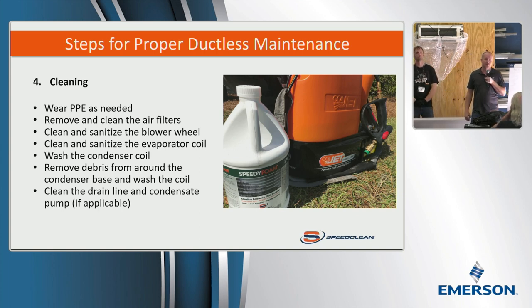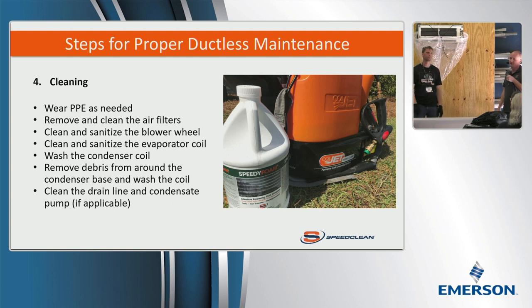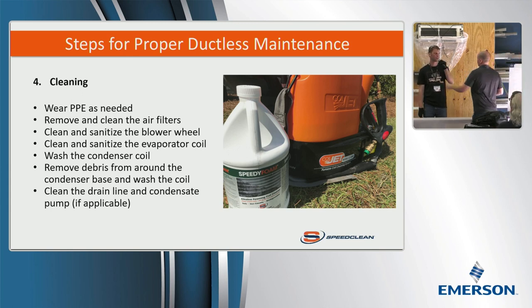No, there are foaming cleaners that are still neutral, or very close to neutral. I don't know exactly what the pH is, but you want something that's not advertised as alkaline. It's generally the strong alkaline cleaners that are the crazy foaming ones, the ones that look really dramatic. But you can still use cleaners that are mildly foaming and still work. Generally speaking, to be safe, I'd suggest using cleaners that specify they're evaporator cleaners—those are your safest ones. They'll be the most neutral and cause the least corrosion. I like evaporator cleaners. Anything that says it's an evaporator self-rinse option is also going to be mild, because it's designed to sit on the coil, so you can use that too. And again, you'll find your favorite products that work best for you.